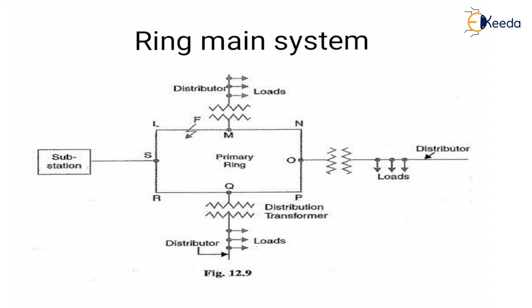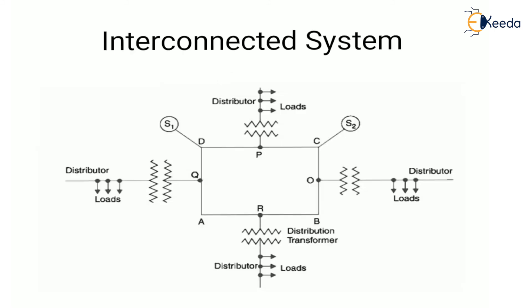The ring main system offers two advantages: less voltage fluctuation at consumer terminals, and reliability — if a fault occurs, continuity of supply can still be maintained through the other side. Next is the interconnected system — when the feeder ring is energized by two or more generator stations or substations, it is called the interconnected system. The distributors are connected to points O, P, Q, and R of the feeder ring through distribution transformers.